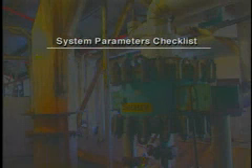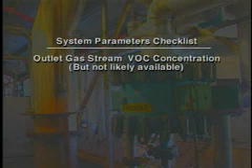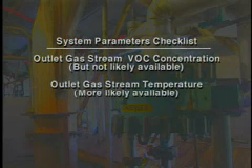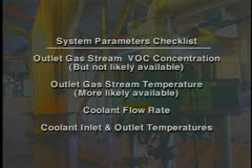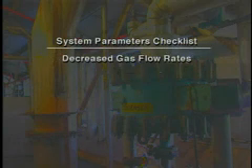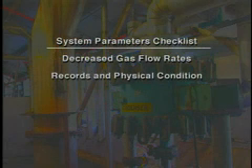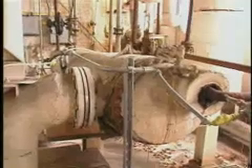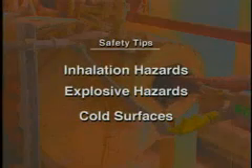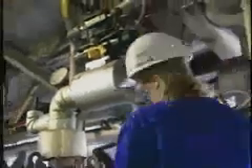To review, to determine if the condensation system is working properly, field personnel should observe if possible the outlet gas stream VOC concentration, though it is not likely available. The outlet gas stream temperature is more likely available. Indirect indicators of efficiency include the coolant flow rate and the coolant inlet and outlet temperatures. Decreased gas flow rates will reduce the capturing of the contaminant. As with any inspection of an air pollution control device, attention must be given to the system's records, physical condition, and compliance with applicable rules. Condensation systems used for air pollution control have many safety considerations, including inhalation hazards, explosive hazards, and cold surfaces. Further training and experience will be necessary to complete all field tasks safely.